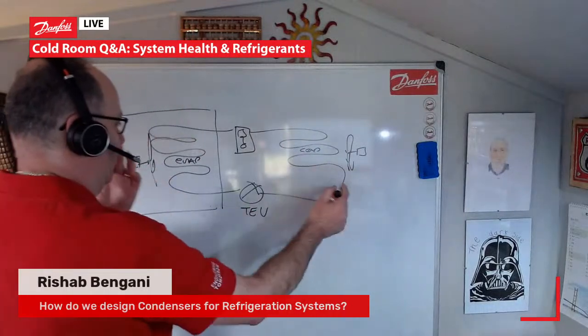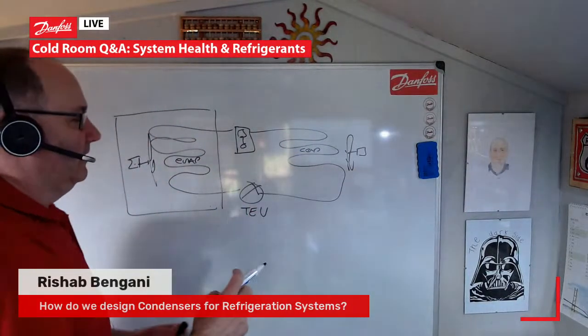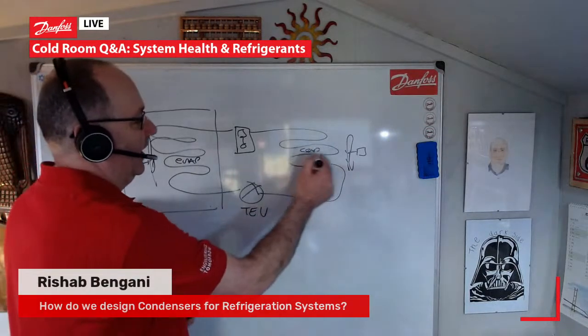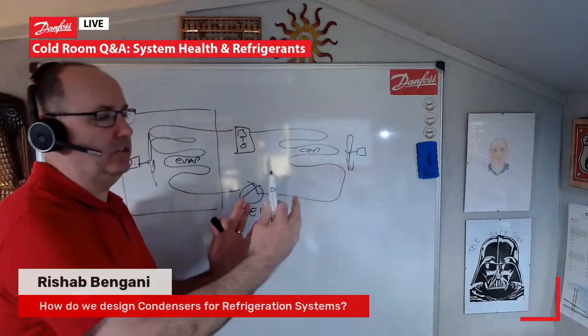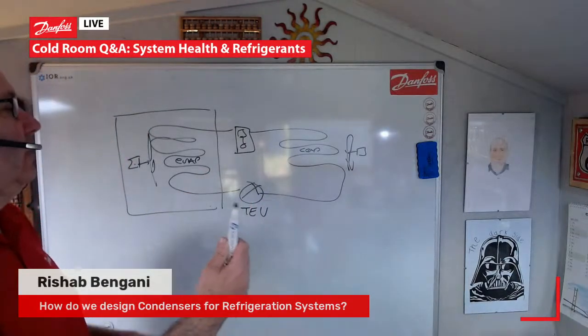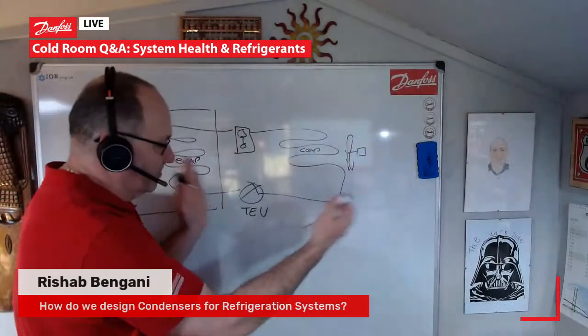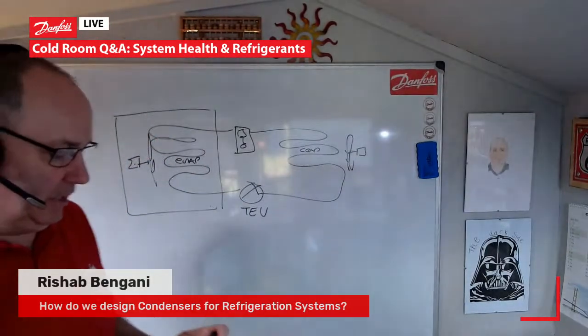Regarding the pipe flow and the direction and the pipe size and all of that, that then comes down to how physically large you'd like your condenser to be or how small it needs to be. If it's fin and tube, then you can go smaller pipe, more fins, smaller size. You can go microchannel heat exchanger, which is what we use on our Danfoss condenser units, which for the physical area that they take up, they're quite a high output. So there's various things that we have to take into account for that, Rishab. So I hope that answers that question.